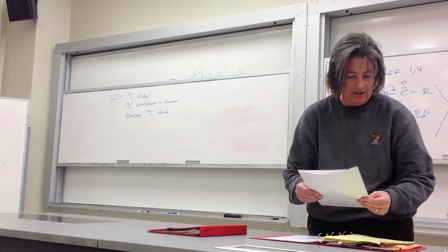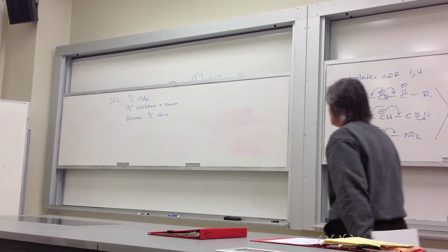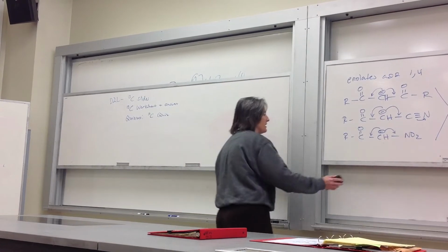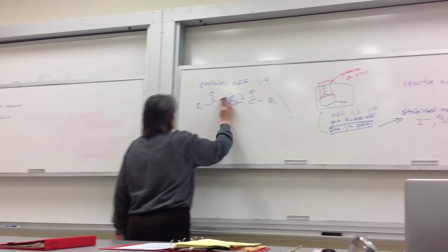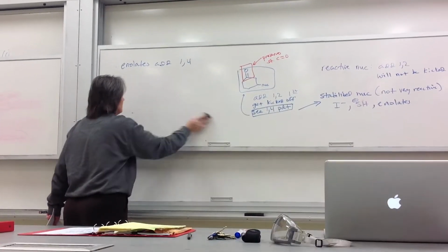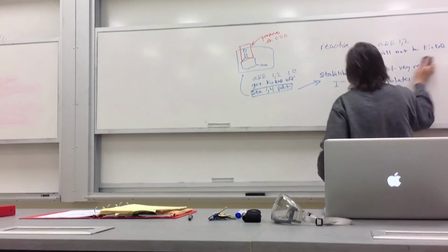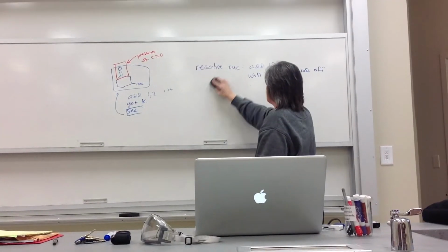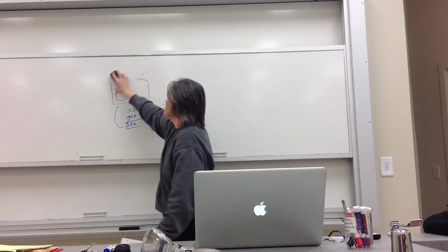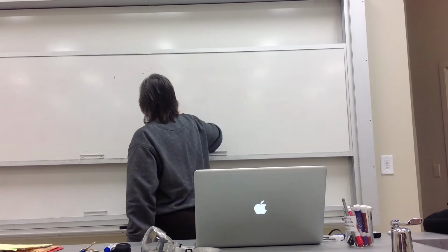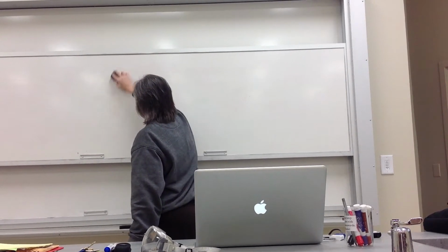Most instruments, when you go into an NMR room, for example, like at Davis, they have proton NMR instruments, and those instruments are capable, with no major changes at all, of also running C13. It's just a question of hitting a button and telling it, yeah, I want C13 instead of proton. So the probe, which is the part of the instrument your sample drops into when it disappears into nowhere, is our probe and our machine can only pick up proton.